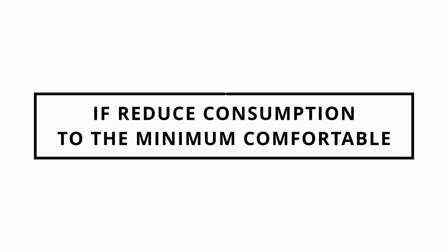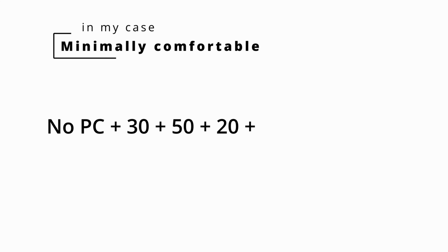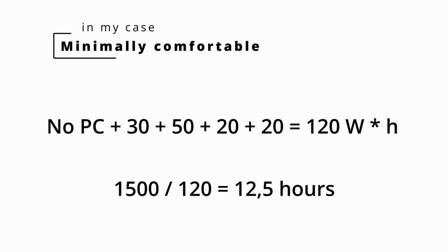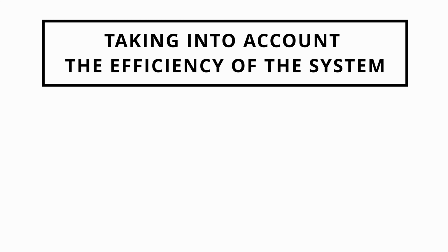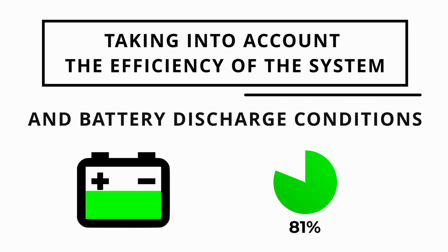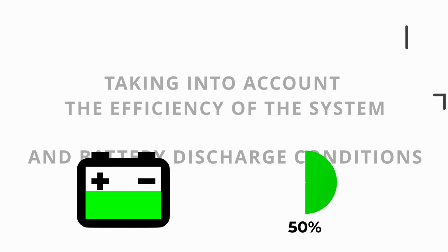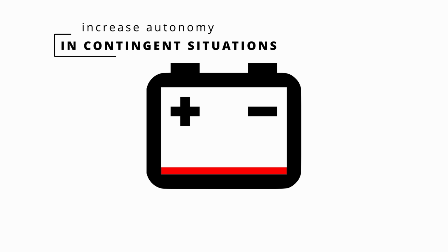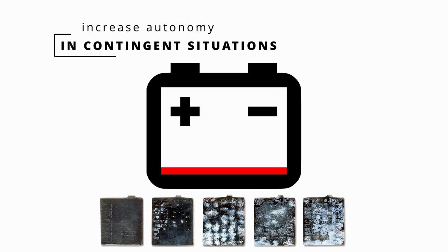If we reduce consumption to the minimum comfortable level, that is, turn off the PC, leave the light on only in 1 room, keep the refrigerator running, and also leave the pump and routers on, we will get about 120 watts per hour, and 1.5 kWh is enough for 12.5 hours. And this already takes into account the efficiency of the system and the condition of discharging the batteries to 50%. In unpredictable situations, it is certainly possible to discharge the batteries to 0, effectively doubling the autonomy. But this will not reflect well on the number of cycles of lead batteries, so it is important to try to avoid doing this. Conclusions.